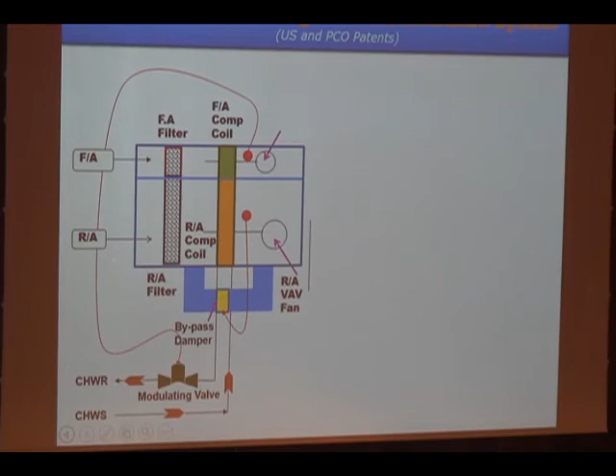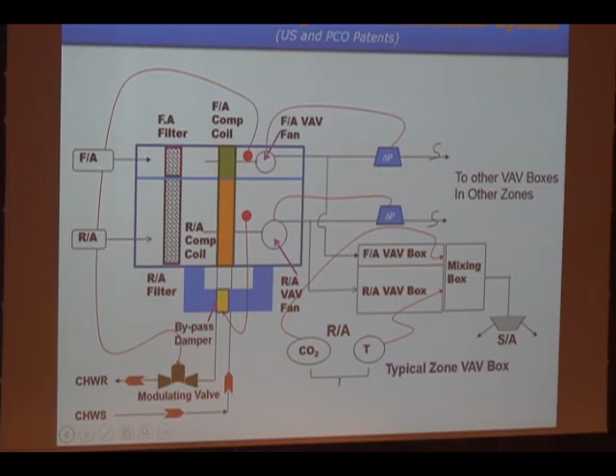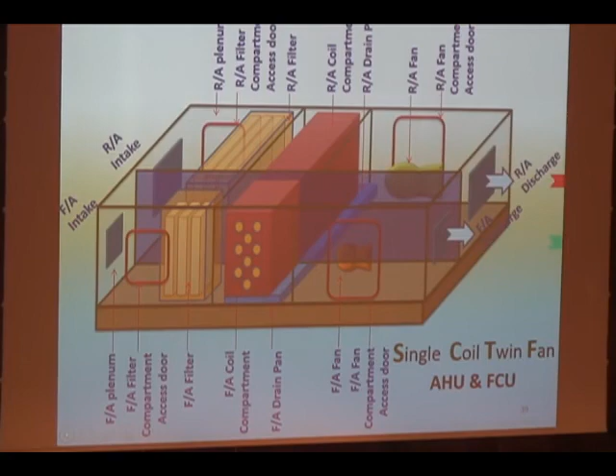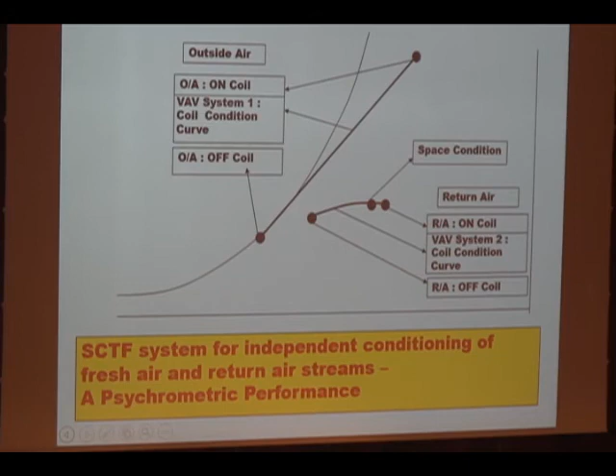So we have a temperature and CO2 sensor. If CO2 is high, we provide more outside air, and if it's low, we reduce it. What happens in one zone doesn't affect an adjacent or adjoining zone. So it's taking the concept of demand ventilation right up to the individual occupied zones. We have a means of some bypass arrangement here to take care of cooling capacity management if you want to. And here is just a way in which this thing works through the air handling unit. And single coil twin fan, we have had a couple of installations as well, and it seems to be providing good results because the outside air can be pulled down separately. The sensible load, which is really what the recirculated cooling air is handling, allows us to manage them quite separately.